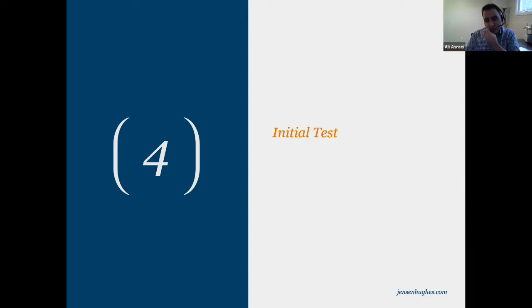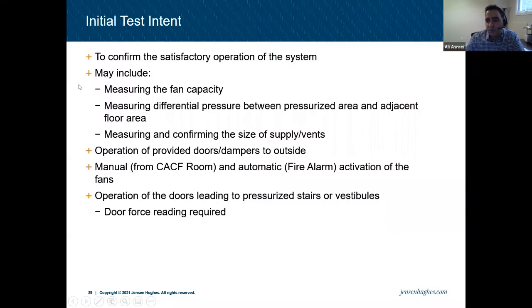All right, so let's continue with initial tests. Let's say we're going to have to do a test in a building. Again, we call it an initial test. This test is to confirm the satisfactory operation of the system. That may include measuring the fan capacity. We may have to do that. Measuring differential pressure between the pressurized area and the adjacent floor area. Let's say they say a vestibule is pressurized. We have to make sure that there's enough differential pressure between this vestibule and the adjacent floor area. Or it's just a little fan blowing some air. It's not sufficient.